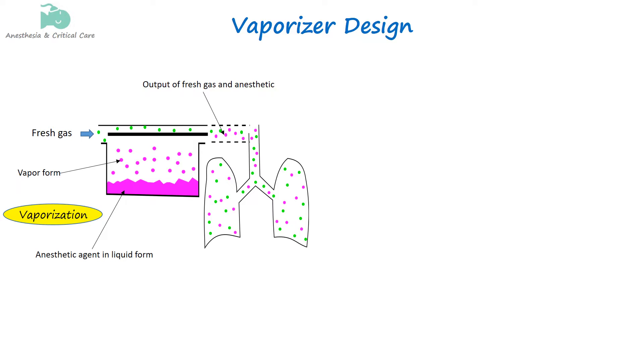The purpose of a vaporizer is to add anesthetic vapor into the fresh gas flow in a way that the output of the vaporizer delivers the set concentration of the anesthetic agent accurately.